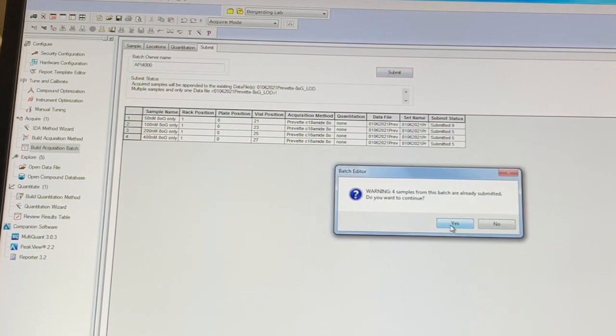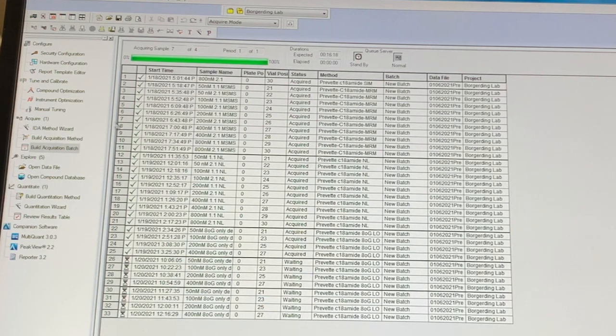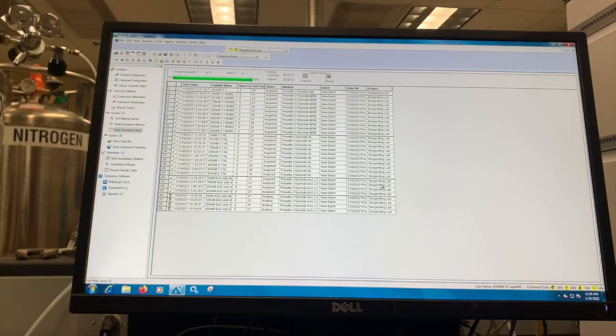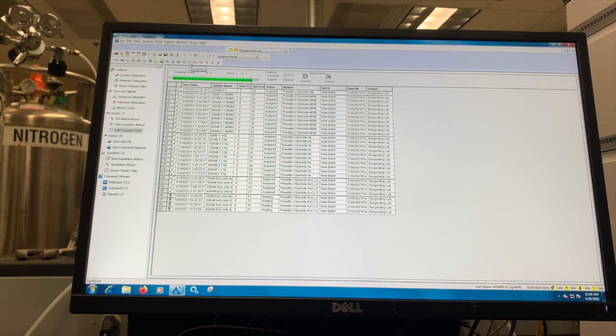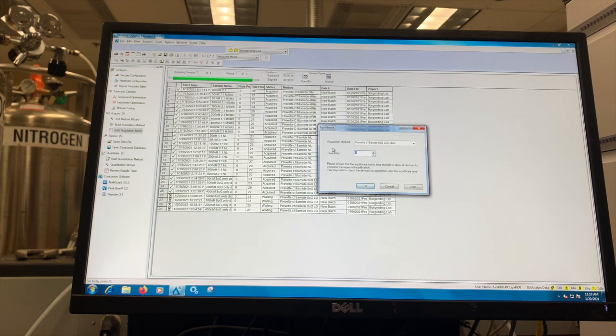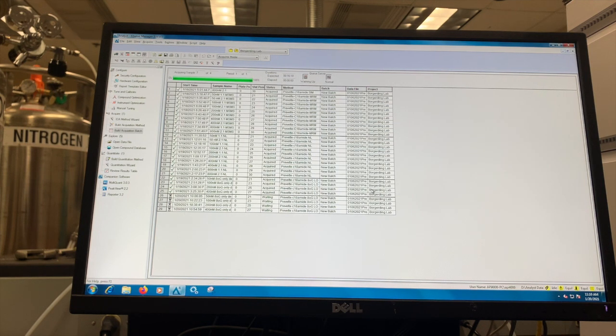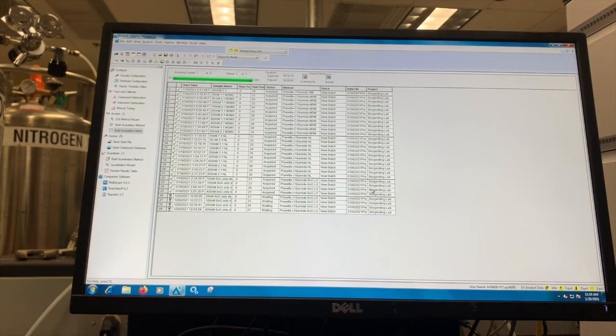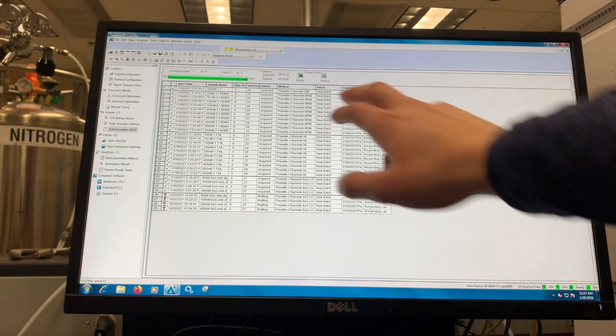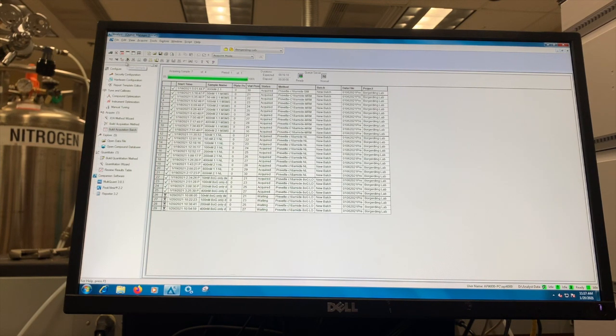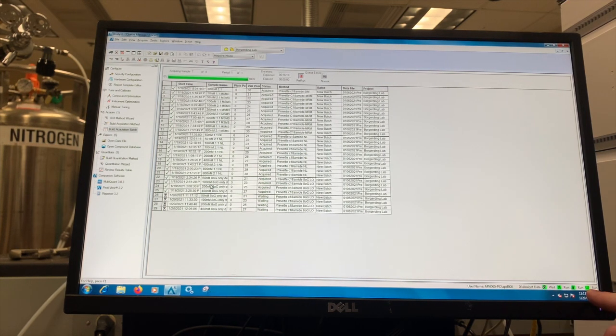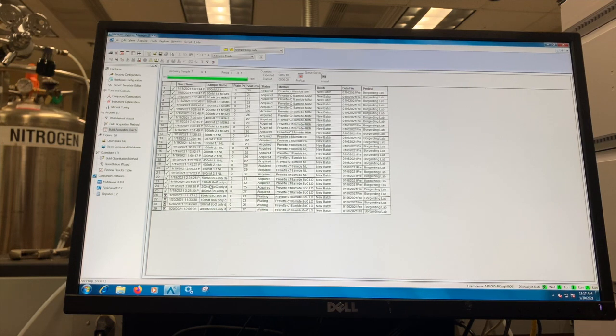And then finally we need to set the acquisition method that we want to use. So here I'm just using this one. So we've set the set name, sample names, vial position, as well as method and so now we are ready to submit. So I can submit these samples and now they show up on the queue here. Now that our samples are submitted we can first click on this icon here, it's the equilibrate icon and I usually set this for five to seven minutes just to make sure that the mass spec is nice and warmed up before my first sample hits it. And you'll notice that the queue server emblem there changes to say warming up. And finally when the equilibration is done this will turn to ready and then we can click the start sample icon over here. And all of these turn to green which means that your LC-MS and all the parameters are looking good and your sample will run.